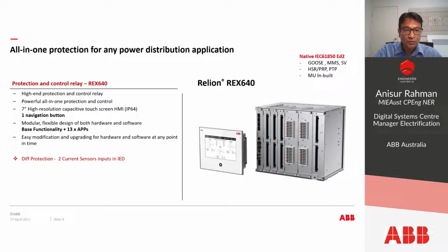For better protection and control, we use our high end protection and control relays. The REX 640 is an all in one protection relay for any power distribution application. These relays are part of our Relion series, and they support native IEC 61850 edition 2, meaning they support GOOSE, MMS and Sample Value, and they also provide HSR, PRP and PTP redundancy, and finally the merging unit is inbuilt. So we use all these capabilities to make our LV and MV boards digitalized.